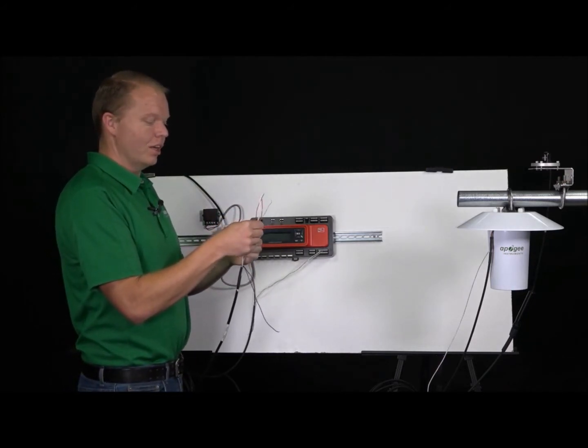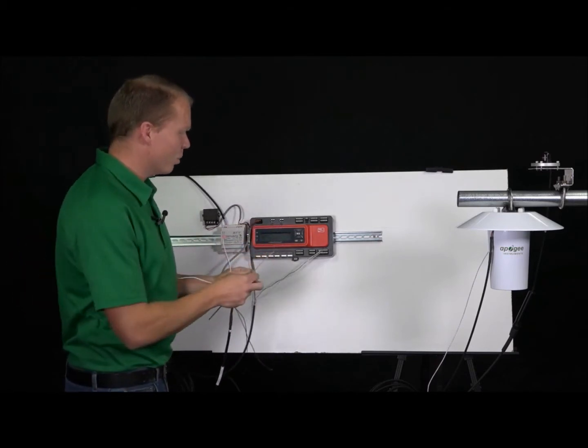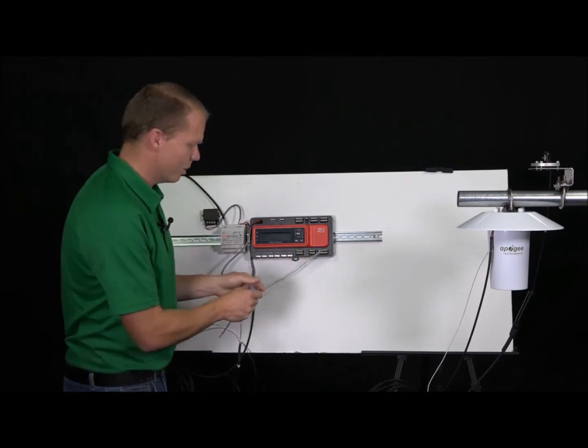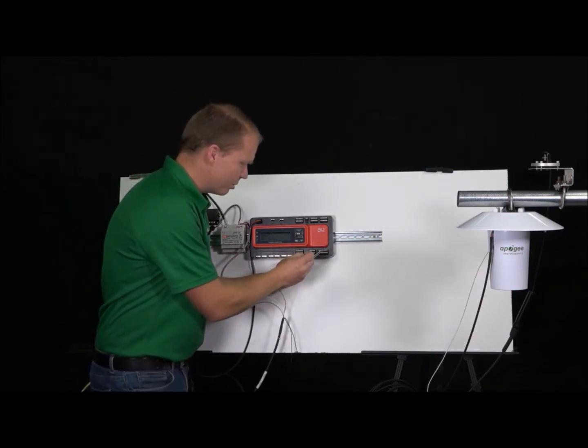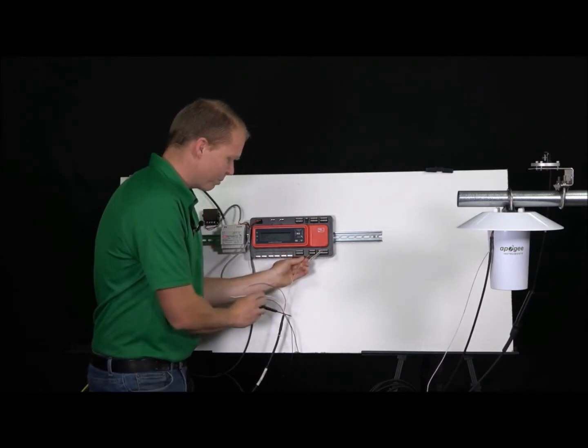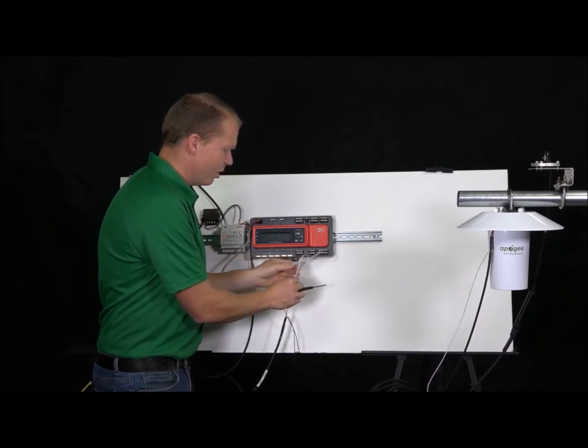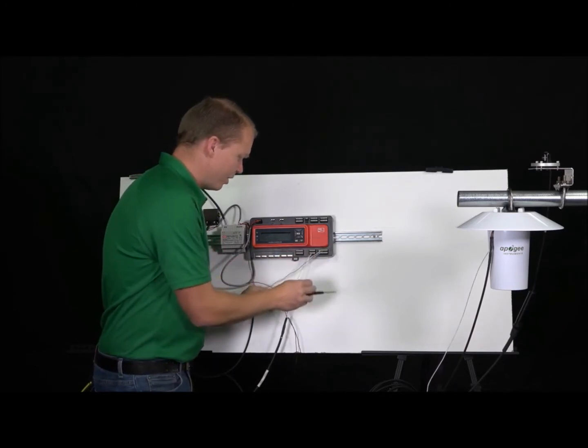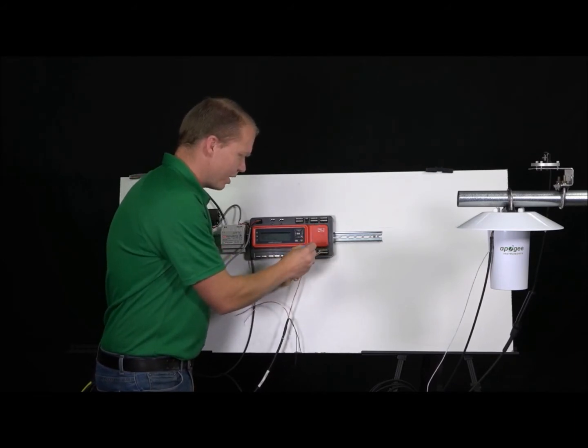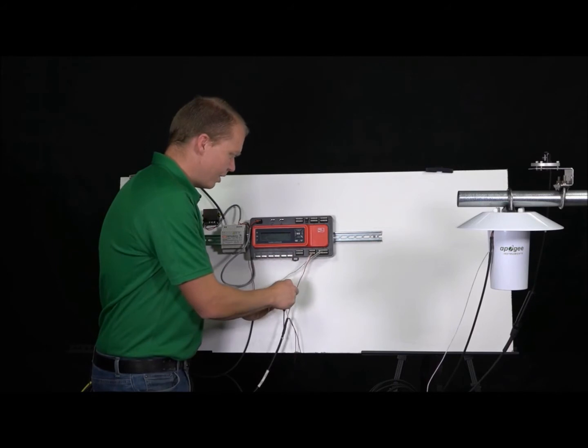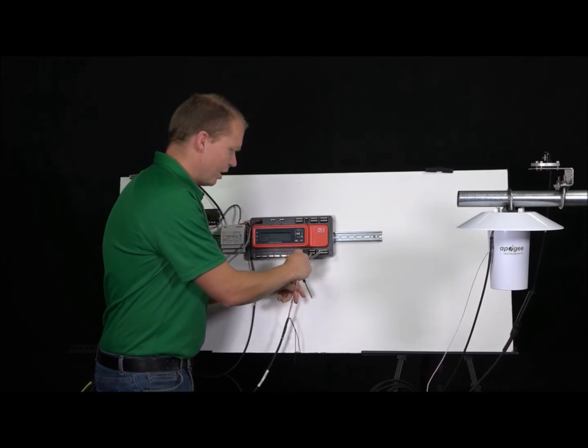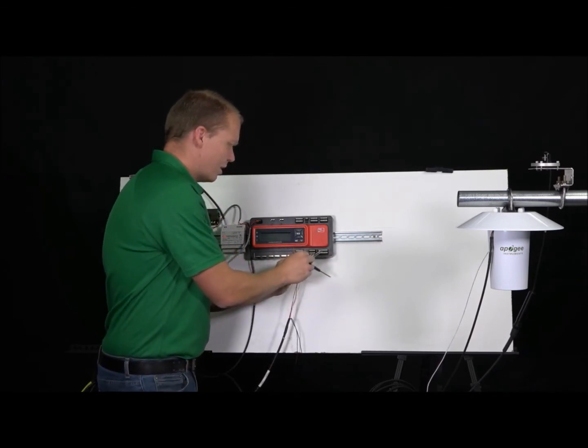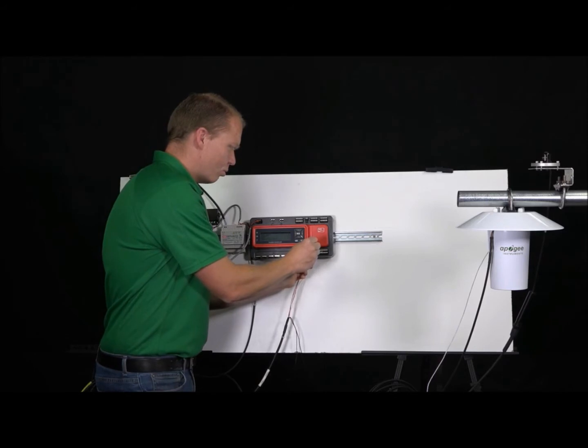We'll start with the shield and we're going to be working on terminal X7 down here and we're going to start on row B which is the bottom one. The first terminal here is going to be the shield and then the next one is going to be the white conductor. It actually doesn't matter which white conductor, you can choose either. Then the next one is going to be a red conductor and again it doesn't matter, you can choose either. Then we can choose the other white conductor that goes in the fourth one and then the last one is the other red.